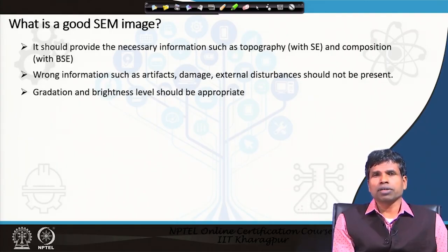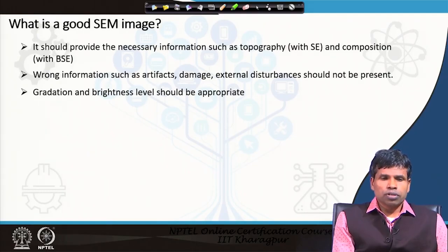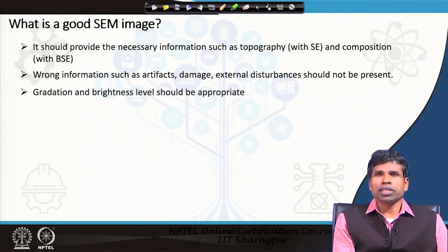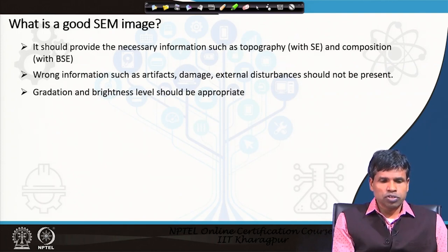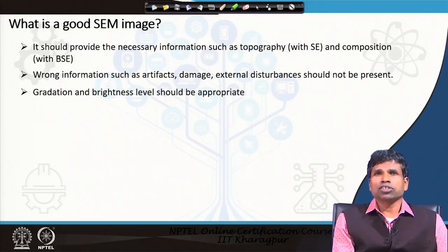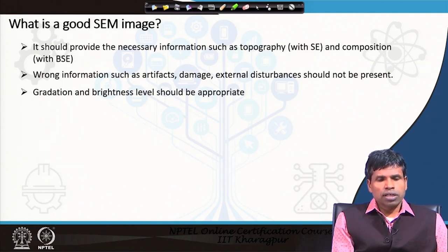Higher atomic number means more backscattered electron yield and those regions will appear much brighter, as you have seen in previous lectures. The SEM image should provide the information we need from our specimen. Additionally, artifacts, damage, and external disturbances should not be present, and we should have a gradation and brightness level that is appropriate — this is what is important for a good SEM image.